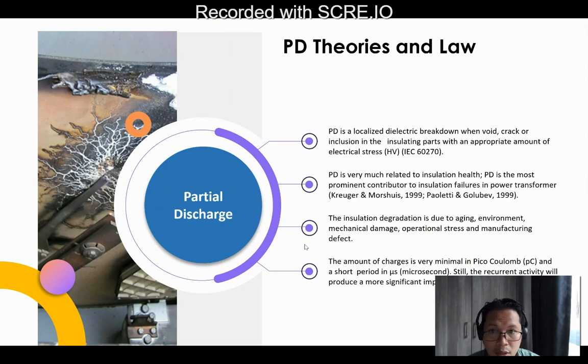Before I continue, let me talk about PD, or partial discharge. PD is a localized dielectric breakdown when our transformer has voids, cracks or inclusions, especially in the insulating part. It keeps increasing when we have an appropriate amount of electrical and mechanical stresses. According to Kreuger and Morshuis, Paoletti and Golubev, PD is related to insulation health and is a main contributor to insulation failures in power transformers. The insulation degradation can be due to aging, where the transformer operates more than 10 years, environmental issues, mechanical and operational stress, or earlier causes such as manufacturing defects.